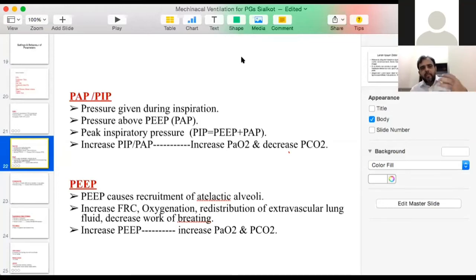Or you can deliver tidal volume and achieve PIP. So you can do both things, one way or the other. If you deliver PIP, it is actually delivering tidal volume. If you deliver tidal volume, it will create pressure. So there is pressure limited ventilation or volume limited ventilation. If you are using pressure mode, you will set PIP, and whatever PIP you set, according to that pressure the volume will be delivered. So you can change tidal volume by changing PIP. Similarly, you can change PIP by changing the delivery of tidal volume. So these are the controllable keys. In pressure mode, you control PIP. In volume mode, you control volume.